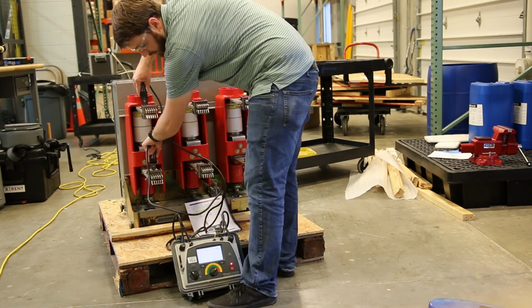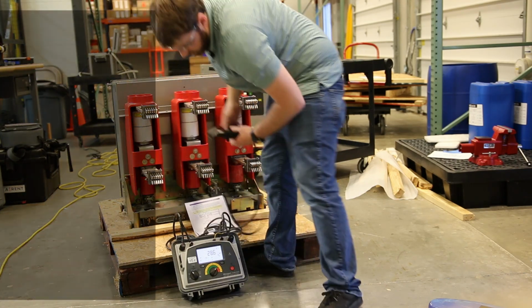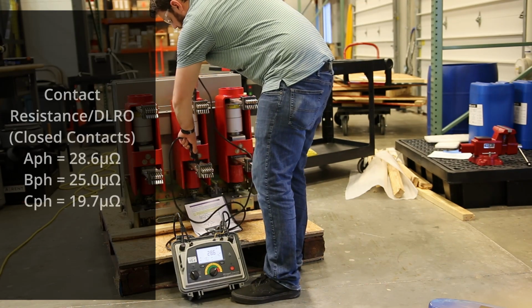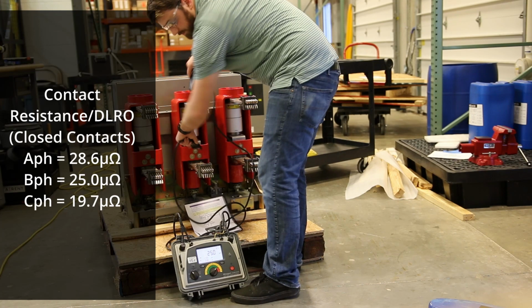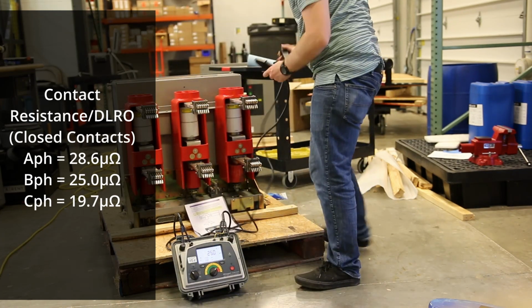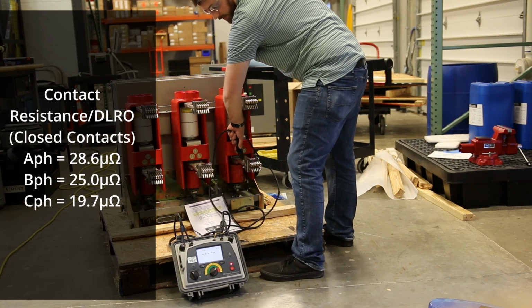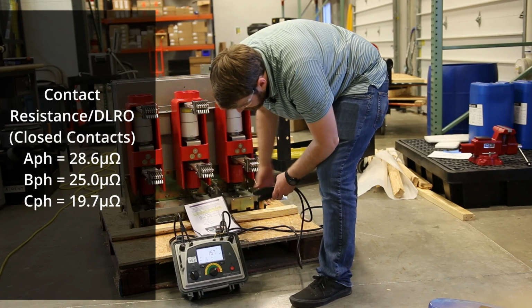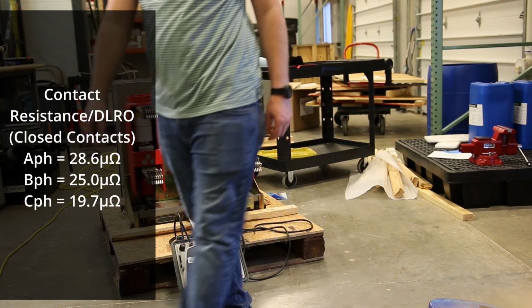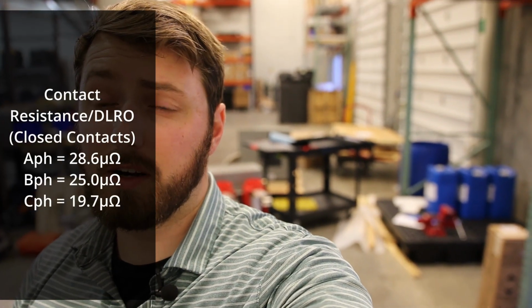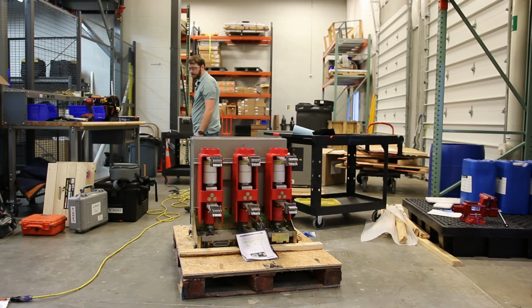So we're gonna go from a consistent spot on all 3 phases. Looking good. This one's 28.6 micro, which is below 50, which should be good. 25.0, looking good. All right, and 19.7. So very similar to our low voltage circuit breaker tests, we need to have all 3 measurements within 50% of each other. The easy way to do that is you start with your lowest value, multiply that by 1.5. Our lowest was 19.7, so as long as the other 2 readings are below 30, just in my head, I know it passes on ductor. So all 3 phases were within 50%. We're good to go. All right, what's up next?